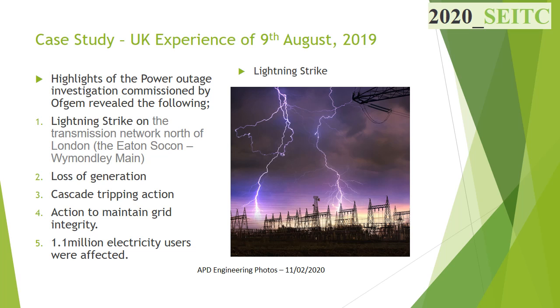Under the regulatory approved Security and Quality of Supply Standards (SQSS), the Electricity System Operator (ESO) has 1 gigawatt of automatic backup power to maintain grid integrity. However, all the backup power and tools ESO deployed to manage the frequency, including 472 megawatts of battery storage, could not stabilize the frequency, which went further down to 48.8 Hz. The secondary backup system, the Low Frequency Demand Disconnection (LFDD) scheme, responded by disconnecting some demand to stabilize the frequency. The action of LFDD put about 5%, that's 1.1 million electricity users of Great Britain, in blackout, representing about 1 gigawatt, to protect the other 95%.